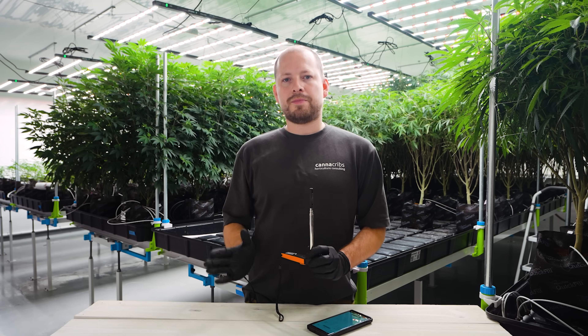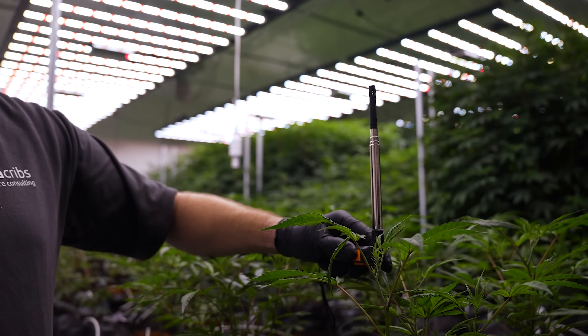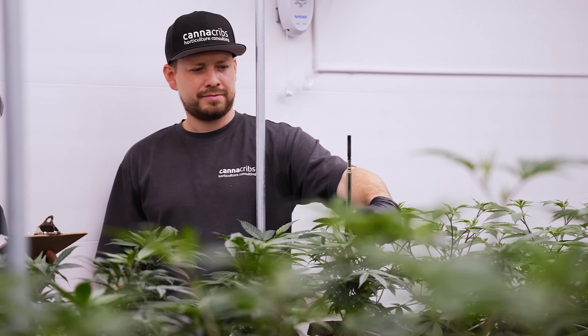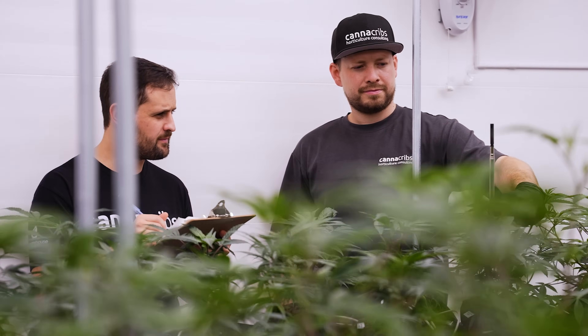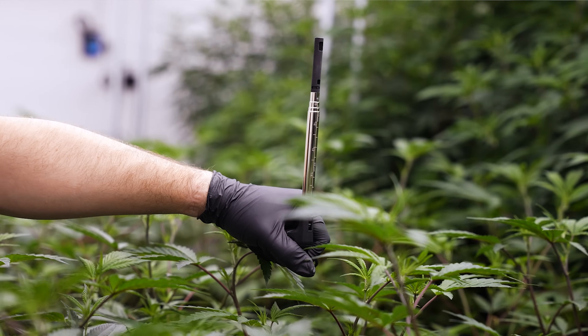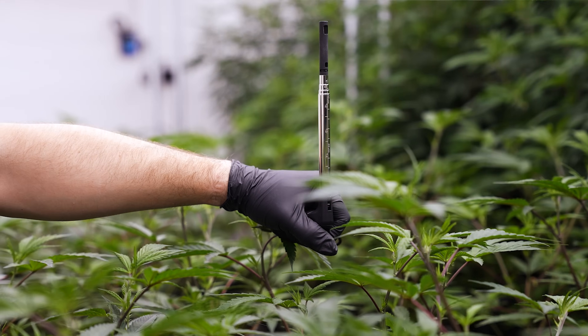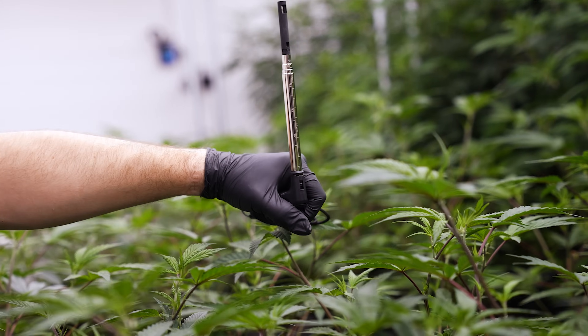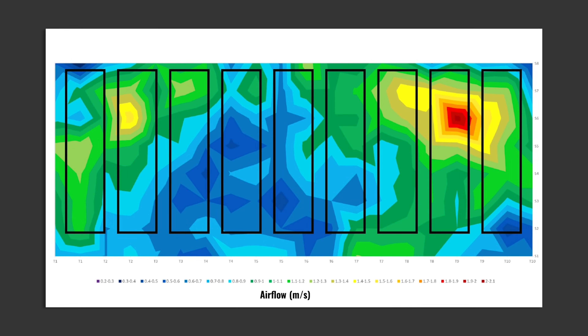We like to measure the airflow at canopy level using a systematic approach. We measure the airflow on each individual table at different points throughout the table. With this data, we can then create a map showing areas of high airflow or low airflow.